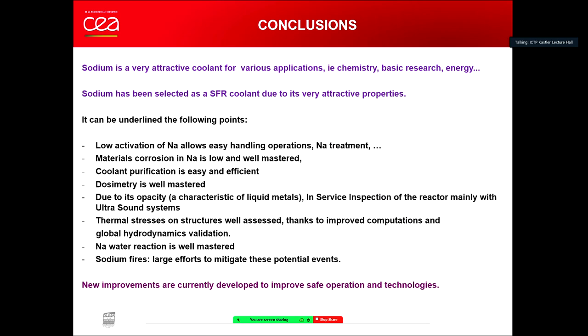Sodium water reaction, I think, is well mastered. Sodium fires, there are large efforts to mitigate these potential events. This is clearly the weak point of sodium. Okay, I think that it's not really the sodium water, because we are able to master that and to use also this reactivity for the treatment, for cleaning, and so on. And even in the steam generator, we consider that now it's okay. But the sodium fires, we have always this point to be addressed in terms of confinement, and the consequence is an increase of the cost also of the system.